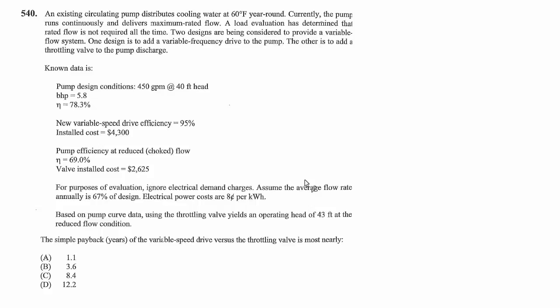An existing circulating pump distributes cooling water at 60 degrees year round. Currently, the pump runs continuously and delivers maximum rated flow. A load evaluation has determined that rated flow is not required all the time. Two designs are being considered to provide a variable flow system. One design is to add a variable frequency drive to the pump. The other is to add a throttling valve to the pump discharge.